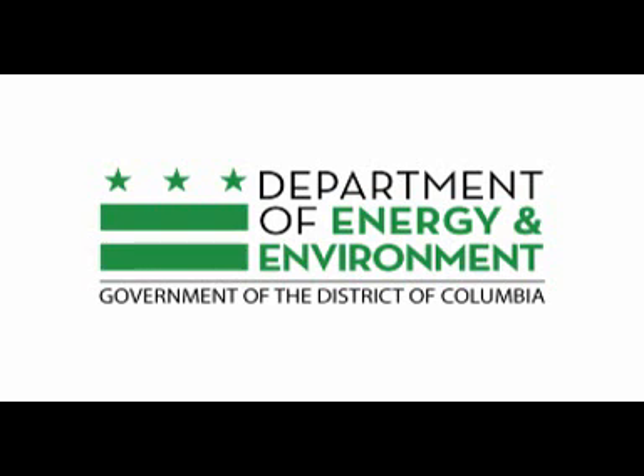I've seen where, and I'm not going to say, it wasn't even Incom, or maybe it was, where they installed their system in hotel rooms. And I could see energy savings for the first month or so, but then because the HVAC systems in the room couldn't get to the comfortable temperature that the people renting the rooms expected as quick as possible, they actually turned off that efficiency measure because their business is to keep people comfortable, right, in a room.